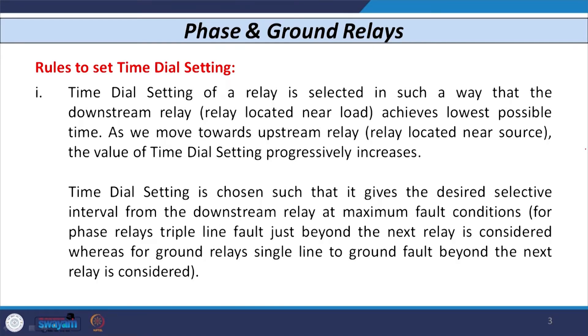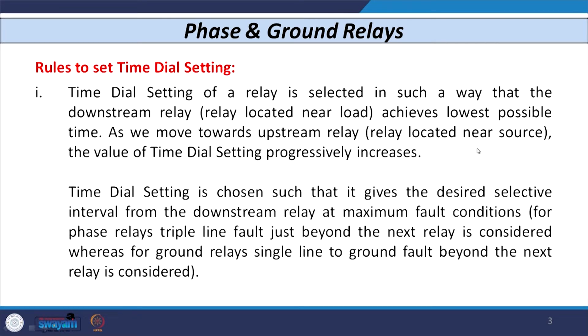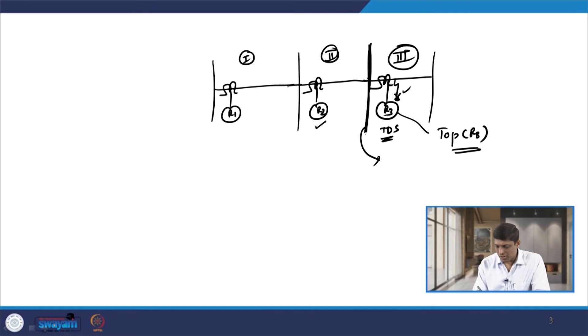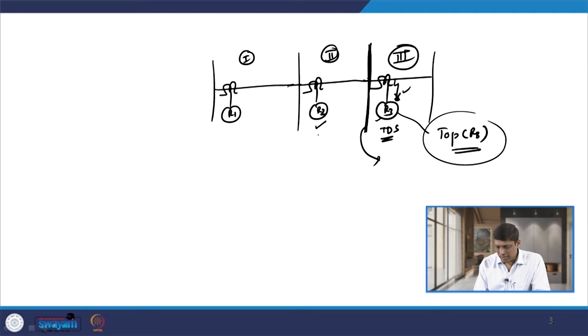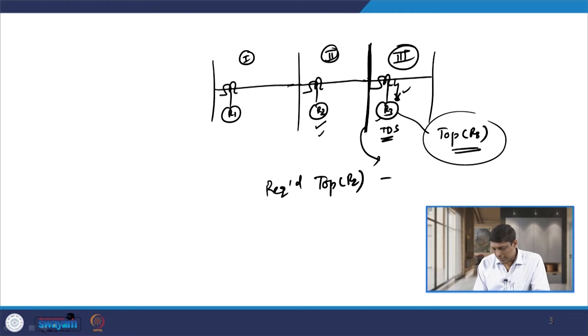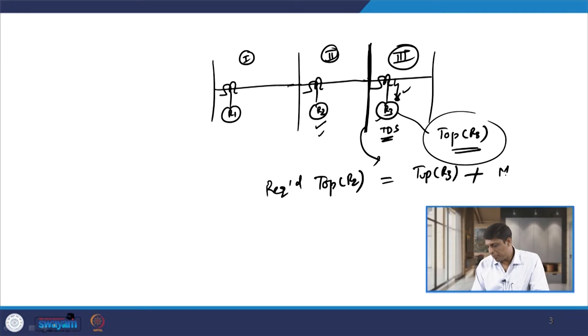For that bus, we calculate the time of operation of relay R3 for maximum fault current conditions. Then, based on this, we decide the time of operation of relay R2. When we decide the time dial setting of one relay with reference to another, we must consider some margin, known as the minimum coordination time interval MCT or coordination time interval CTI. The required time of operation of relay R2 must equal the time of operation of relay R3 plus the CTI.